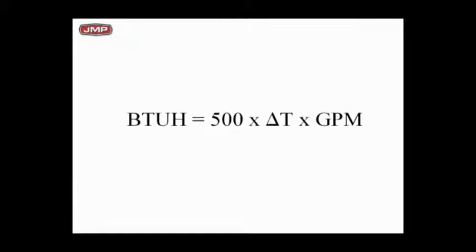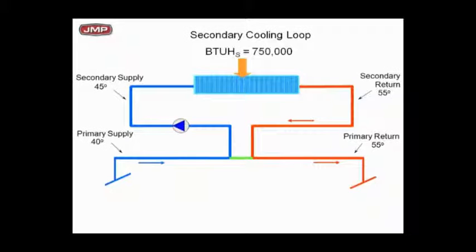Here's your basic formula we kind of went through. I think everybody understands it. If not, take your time to learn it. And let's apply it to a typical primary circuit setup. So you start pulling some of these pieces together. I want to make sure you got this fundamental building block of primary-secondary in your brain. Here we go. I got a crossover bridge here - could be hot water, chilled water. In this case, I'm using chilled water. Got a crossover primary bridge at 40 degrees. I hope to go back to my chiller plant at 55. I'm taking out 750,000 BTUs. I've got a delta-T of 10 degrees on the secondary side. So using Q equals GPM times 500 times delta-T, what are my flow rates I need for each set of pumps and what would be the delta-T?